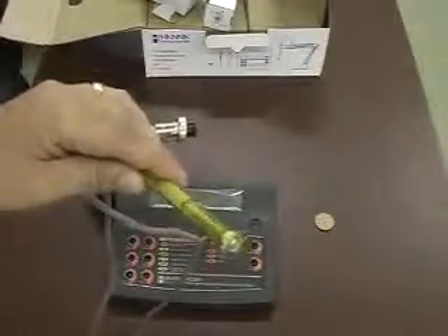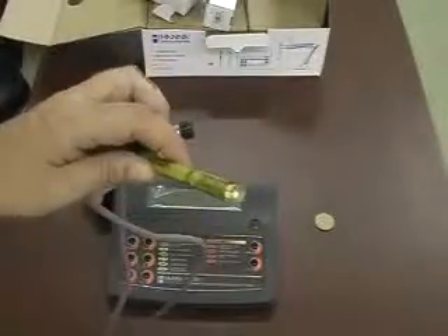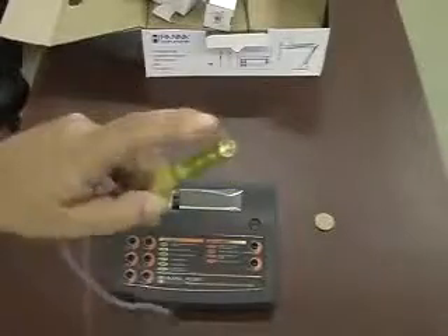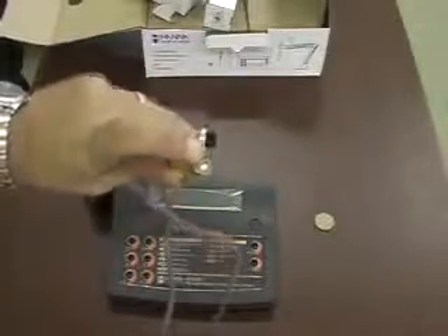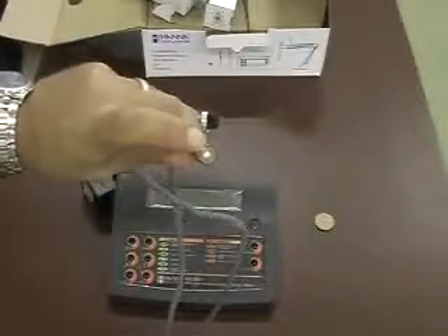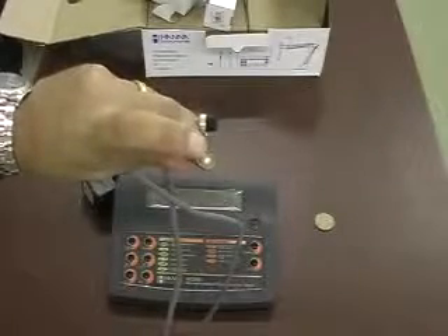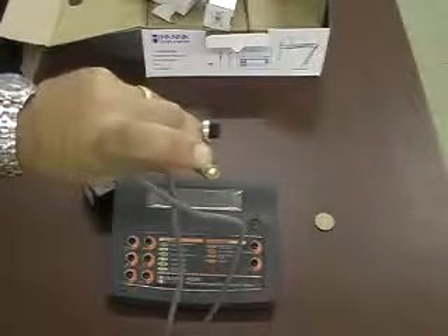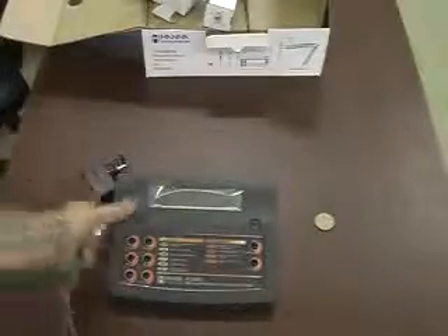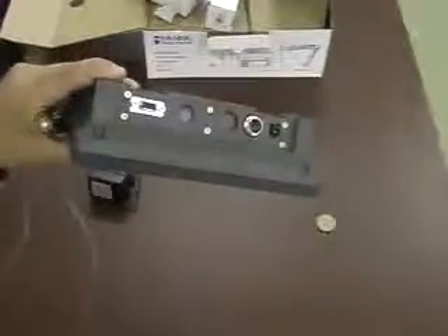In my hand is the conductivity probe. As you can see, there's a DIN connector right over here that plugs into the back of the meter, and at the front end there is a protective plastic insert that should be removed before installation onto the meter and before its use. The connectors on the back plug in there, and then there's a port for the power.